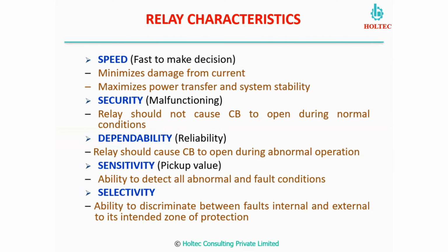Selectivity is the ability to discriminate between faults, whether internal or external, to its intended zone of the protection. This means which circuit breaker or which switchgear it will give the tripping, or which relay has to give tripping to what circuit breaker. So this we can discuss further in the next slide.